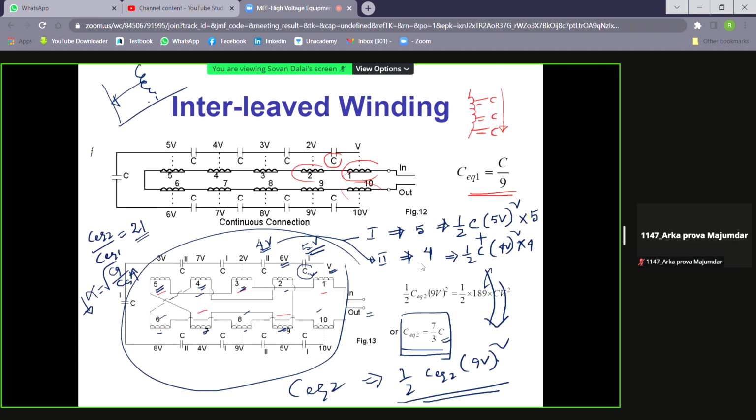So always we improve the potential distribution of the transformer winding by increasing the value of series capacitance only. We don't consider in any design case the effect of the ground capacitance, because it is related with the physical construction of the transformer tank.